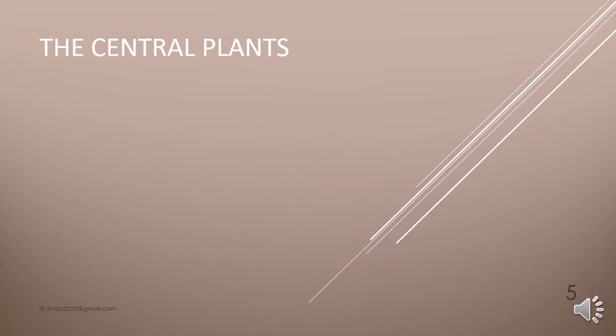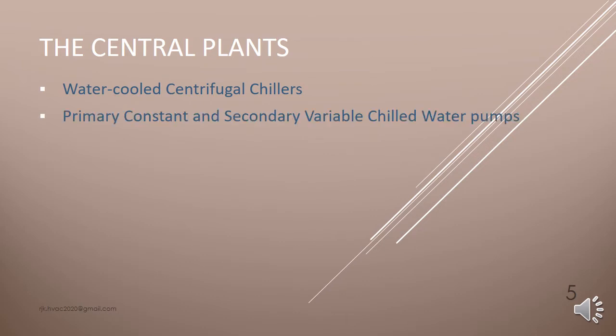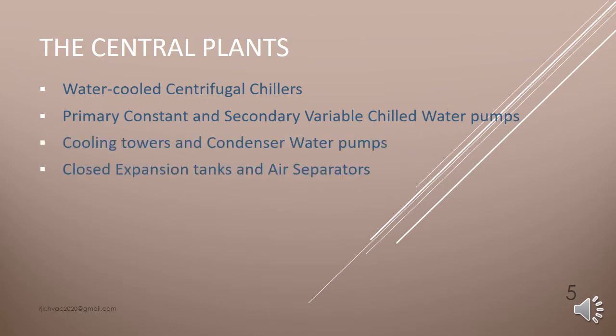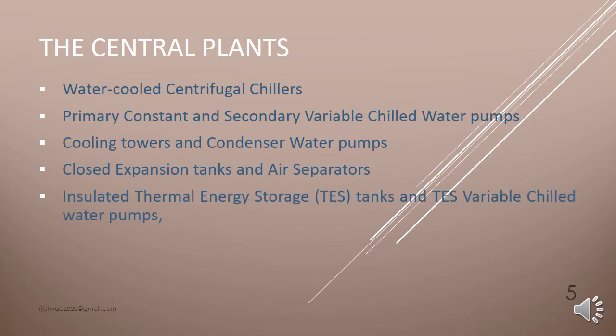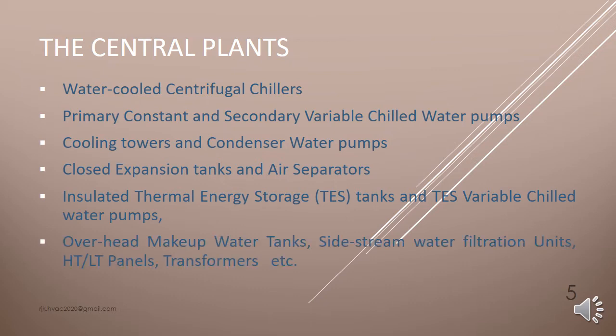The central plant. It comprises of water-cooled centrifugal chillers, primary constant and secondary variable chill water pumps, cooling towers and condenser water pumps, closed expansion tanks and air separators, insulated thermal energy storage tanks and TES variable chilled water pumps, overhead makeup water tanks, side stream water filtration units, HT/LT panels, transformers, etc.